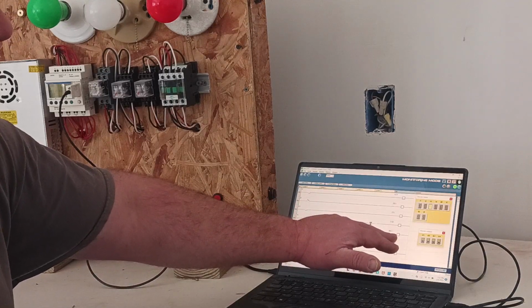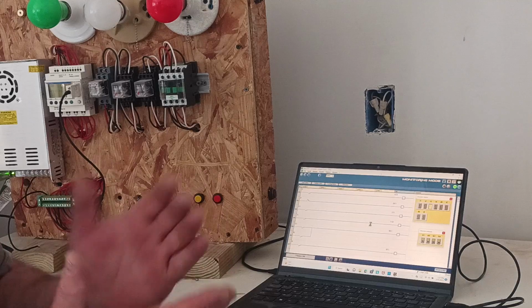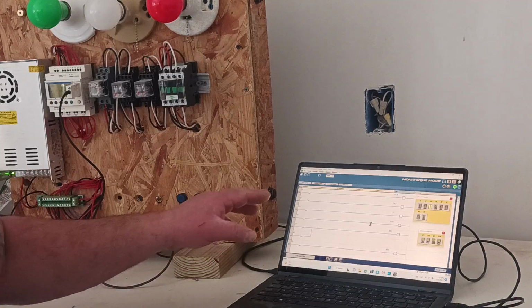See that RC1, it resets counter 1, so that during the time whenever the motor is on to show the next phase of the packaging or whatever we're doing, if other items pass by that photo sensor, we can still keep counting, and then we'll reach our count, and once again the process will get initiated. So I'm gonna show this.